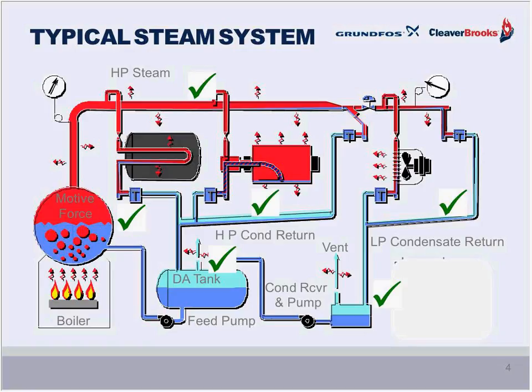Looking at the typical steam system, you can see the point of greatest heat is, of course, the boiler. It's not the only place where impurities precipitate out of the water because of elevating temperatures, thereby corroding or seriously damaging the system. These all have to be checked and mitigated, or the total system can fail and significant energy can be lost, along with costly production time and possibly some product loss.